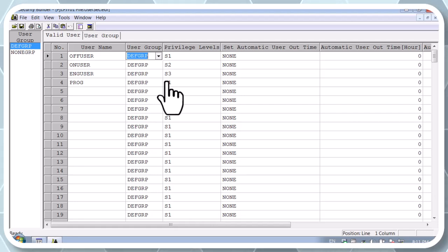And the last one is the username with a program, and he also belongs to the default group. This user is used when you make some configuration in OPC, and it has access for external programs. Commonly, it's used when a user application or external system needs to read data from the Yokogawa system.